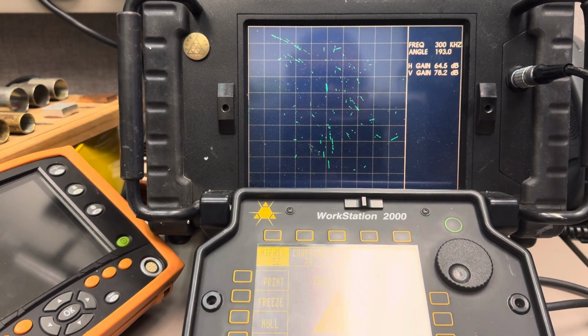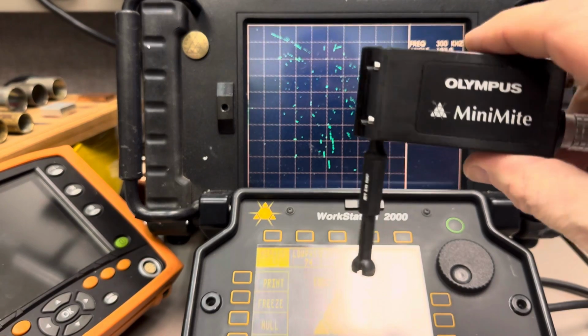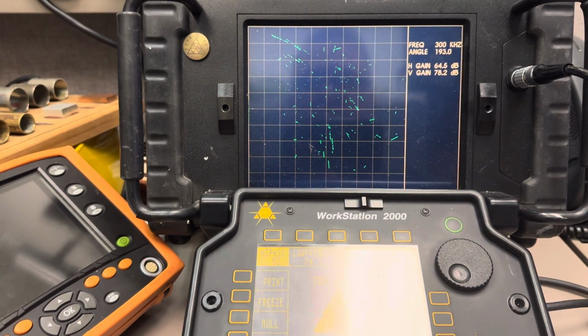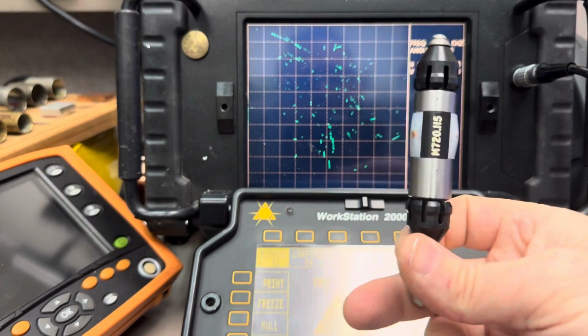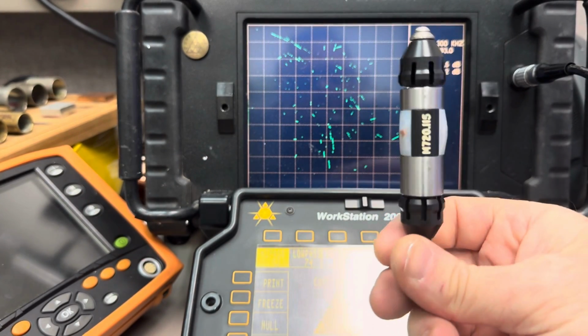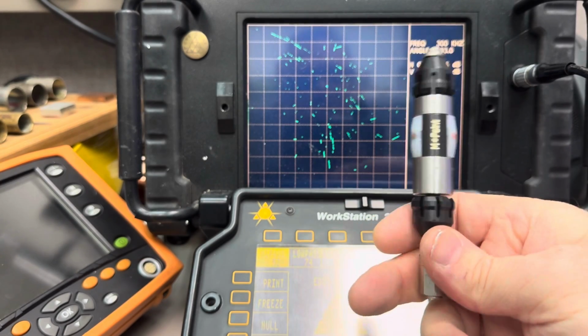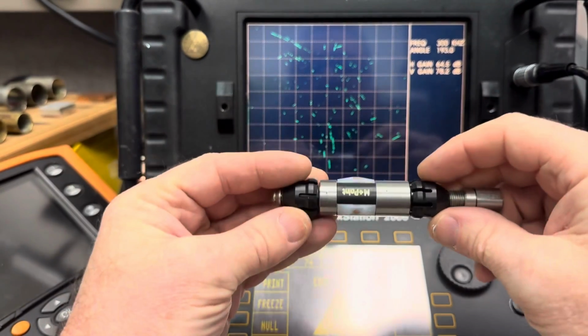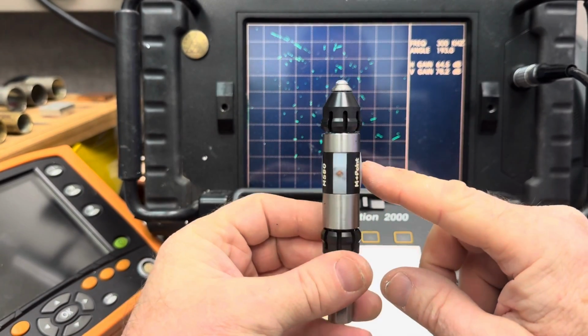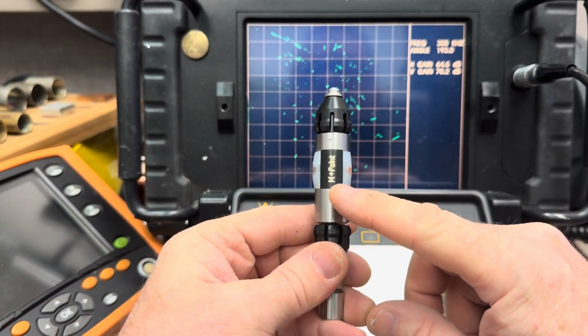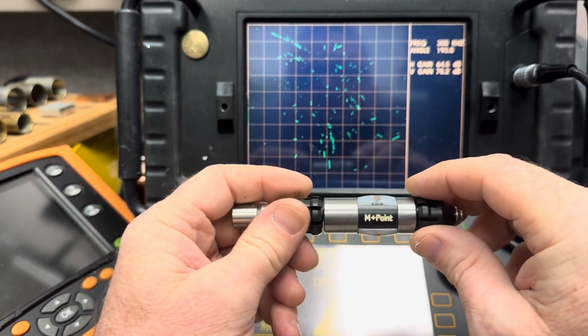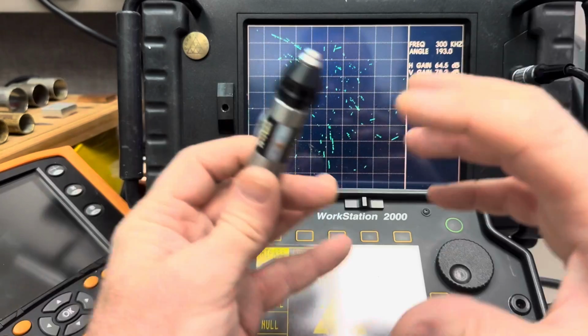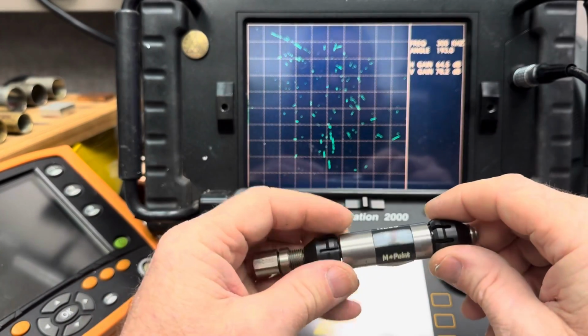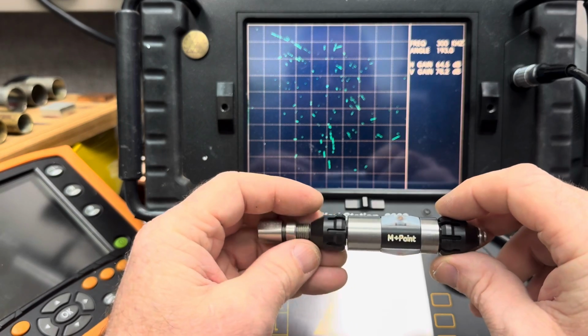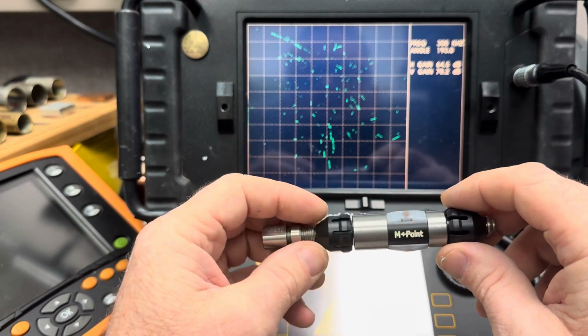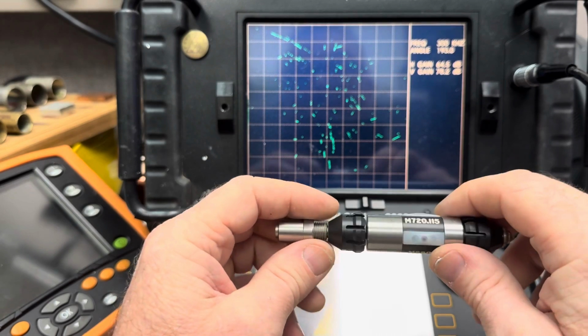So instead of having a probe like this attached to a handheld scanner like this one, your probe would look something more like this. Now this is a straight body probe, and this is called a delta head, I think that's what they called it. Anyway, it has 3 different coils on it. It's got a plus point. See that? A plus point. That's a differential arrangement. It gives you a dual polarity signal for volumetric flaws, and it'll give you a one polarity type of signal for preferentially oriented flaws like axials or circs.